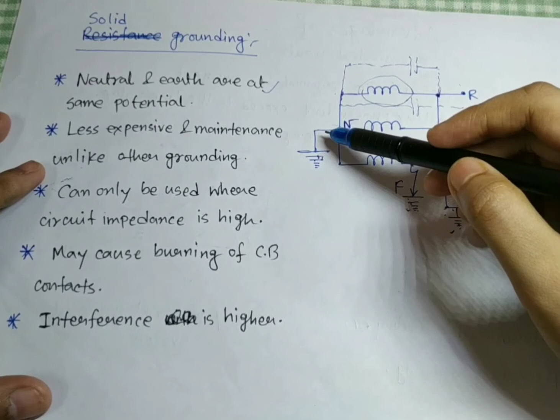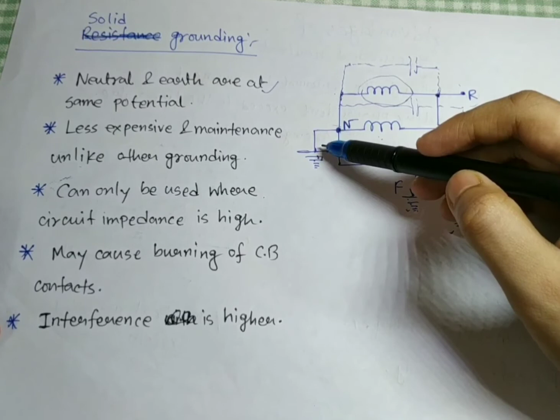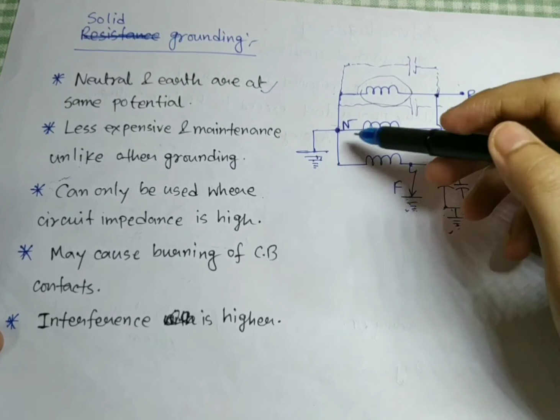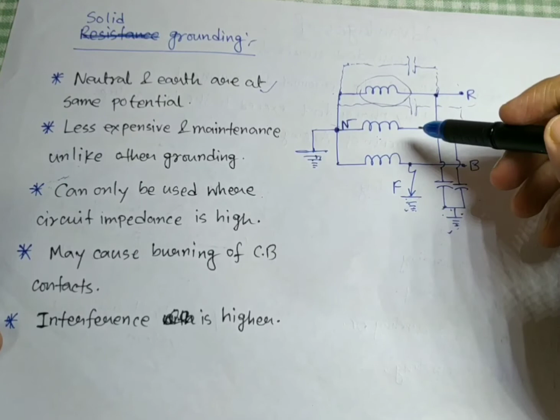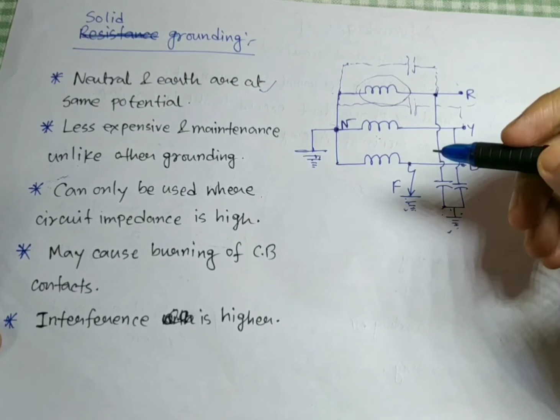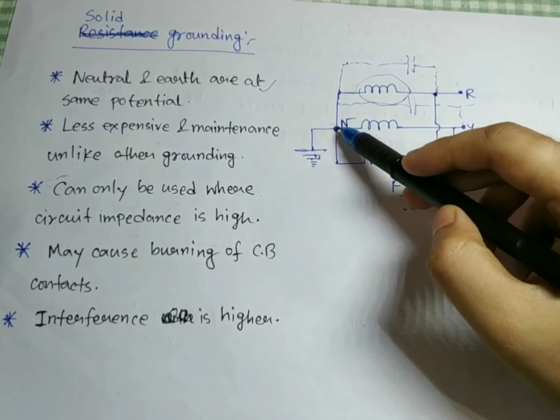The second point is that it can only be used where circuit impedance is high, because here you are directly connecting your neutral with the ground. That means the fault current is going to be very high. Sometimes it is not acceptable to have a very high value of fault current, because it may damage the circuit breaker contacts. So this kind of circuit can only be used where circuit impedance is high, so that the fault current can be limited to a safe value.